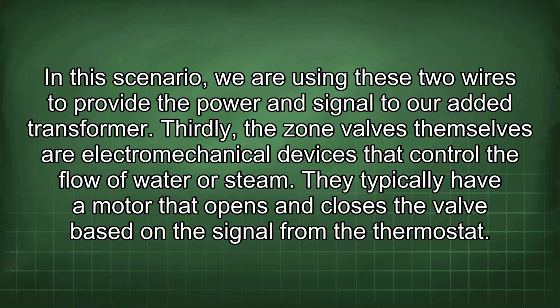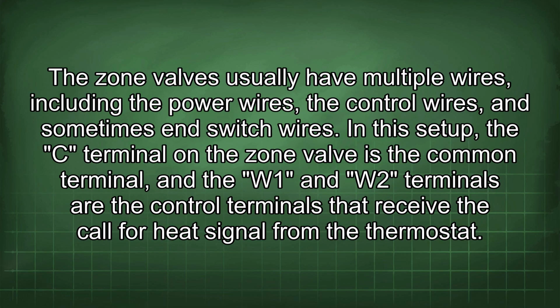They typically have a motor that opens and closes the valve based on the signal from the thermostat. The zone valves usually have multiple wires, including the power wires, the control wires, and sometimes end switch wires. In this setup, the C terminal on the zone valve is the common terminal, and the W1 and W2 terminals are the control terminals that receive the call for heat signal from the thermostat.